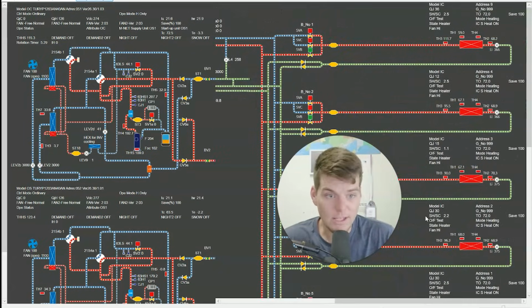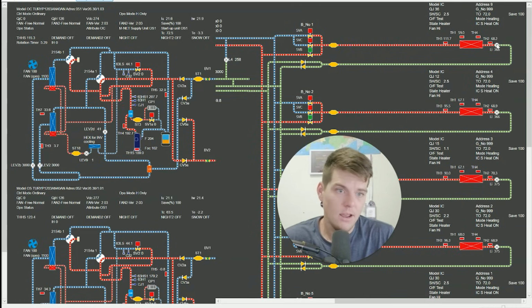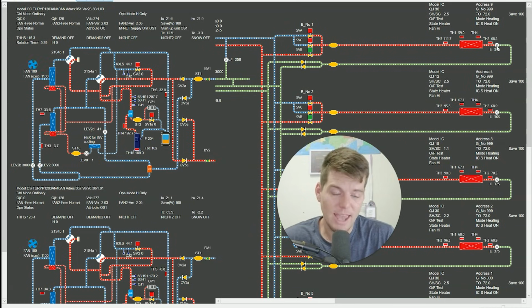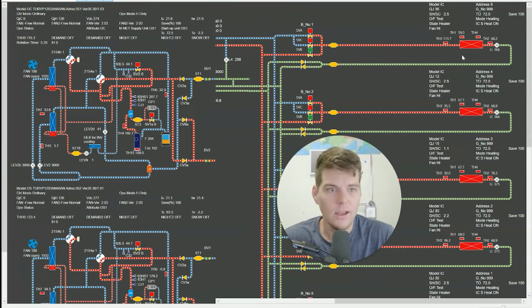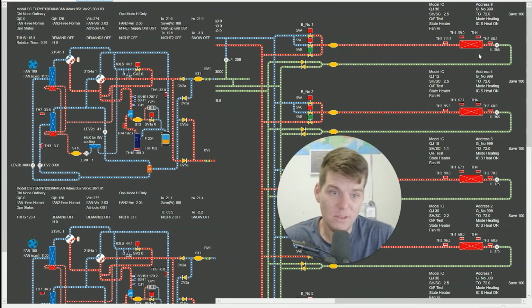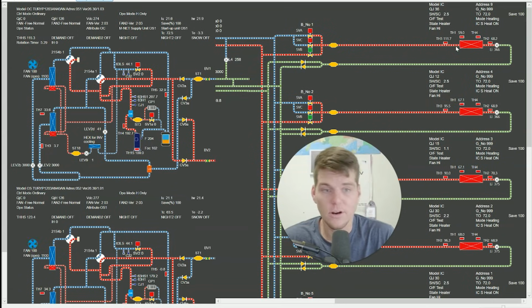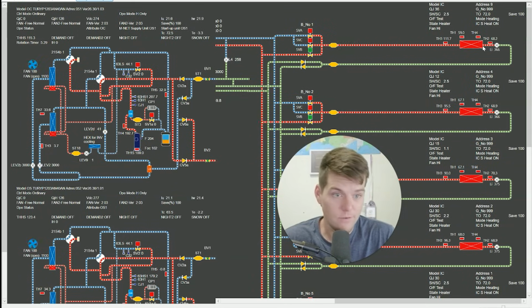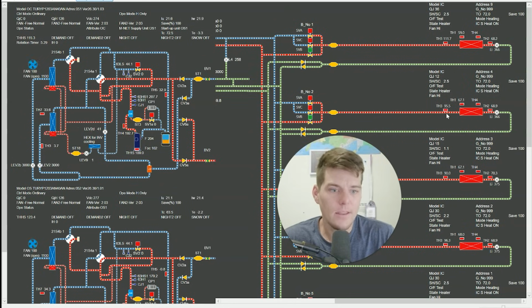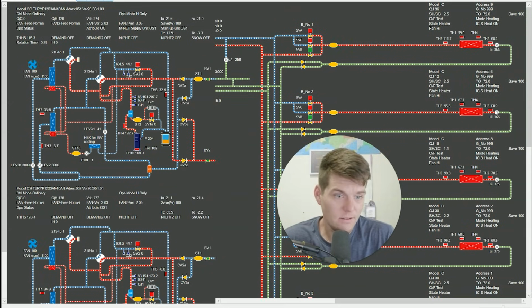And so with that, we can see here it's 111 hot gas coming in, and then leaving, right, is 68.2 degrees. Now that's a heck of a delta, or as you would think, a heck of a subcooling, when that could just be a matter of maybe there's a giant pressure drop across here, maybe there's not enough refrigerant flowing through this, which is clearly the case here. And the same thing here, 95 in, 68 out.